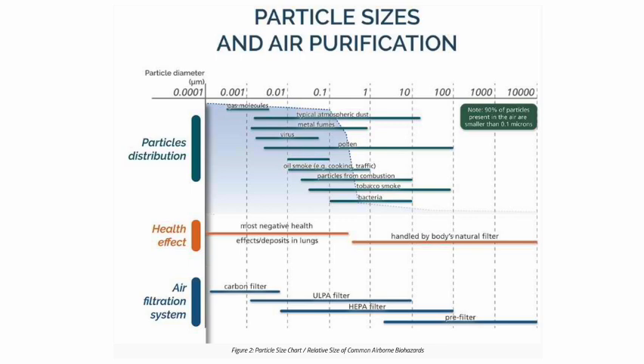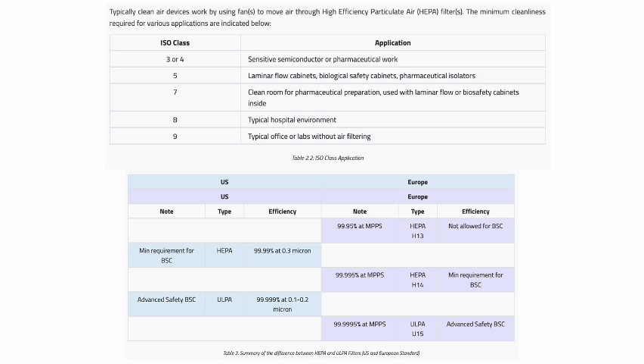But then again, your HEPA filter is adequate in most biosafety cabinets. Only in special work practices is our ULPA used. Okay? So the most internationally recognized standard for clean air is ISO 14644. This is the international standard we follow when choosing what filter should be used in a biosafety cabinet or in a work practice. Under this ISO 14644, ISO class 5 is the standard we use for laminar flow cabinets, biological safety cabinets, and pharmaceutical isolators. Under this ISO class 5, we can determine the efficiency of the HEPA and ULPA filters.